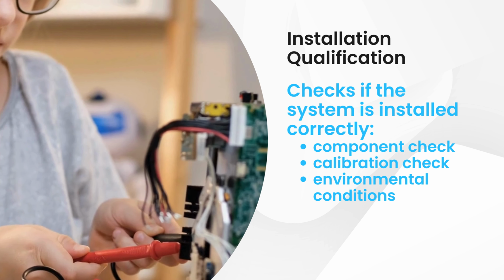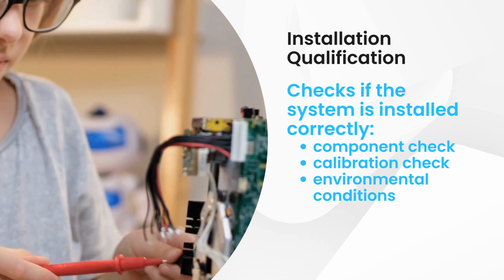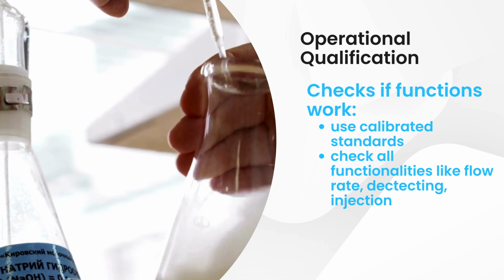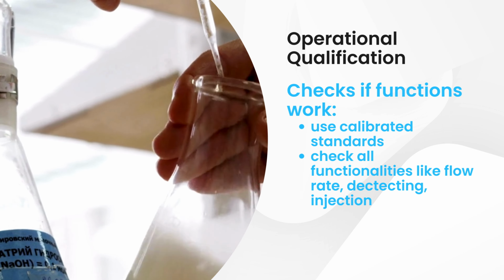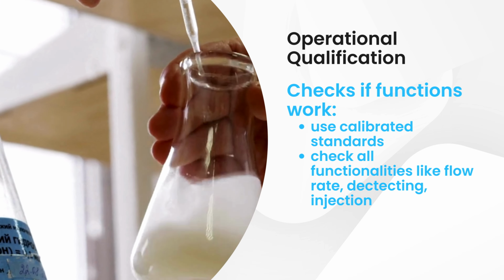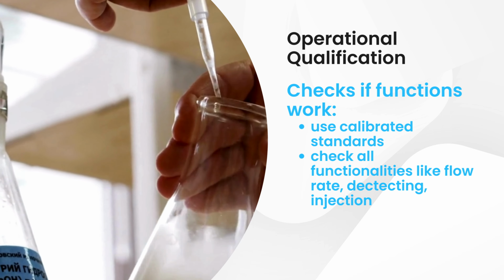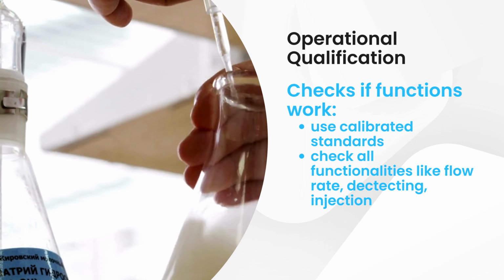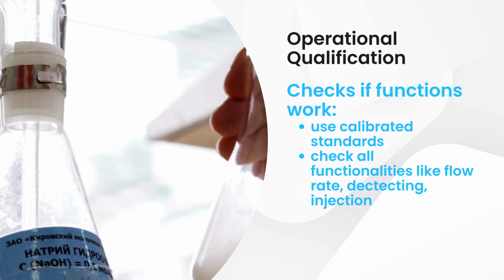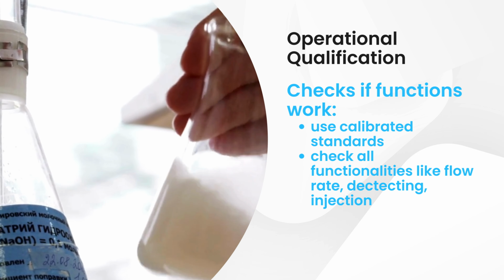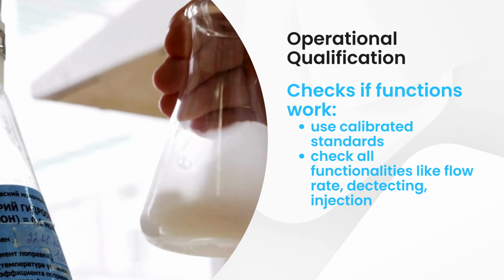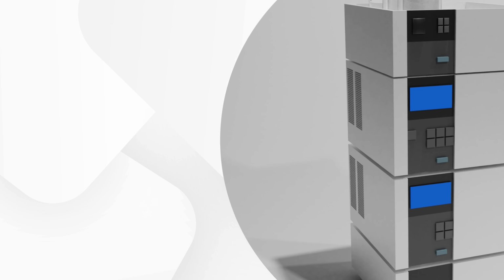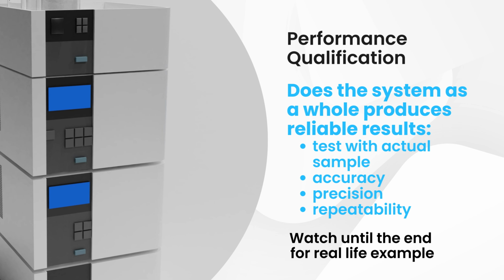3. Operational qualification, OQ. This demonstrates that the HPLC system performs as expected within its operating range. You'll test key parameters like pump flow rate, detector accuracy, and temperature control. 4. Performance qualification, PQ. This confirms that the entire system, including the instrument, software, and your specific analytical method, consistently produces reliable results for your particular application.